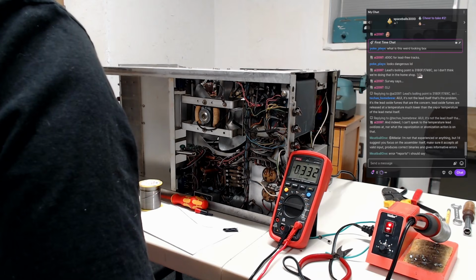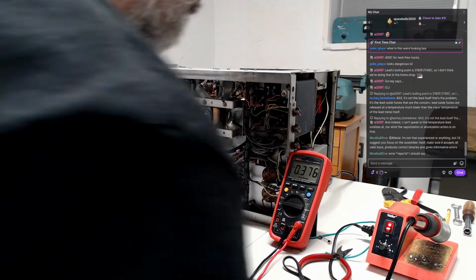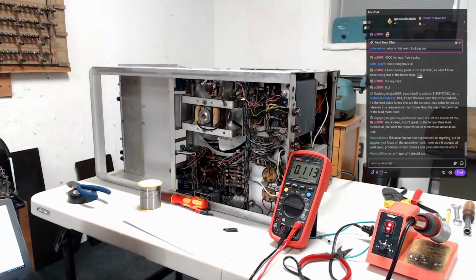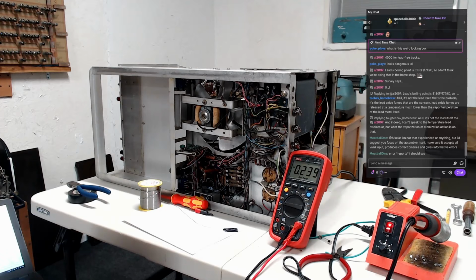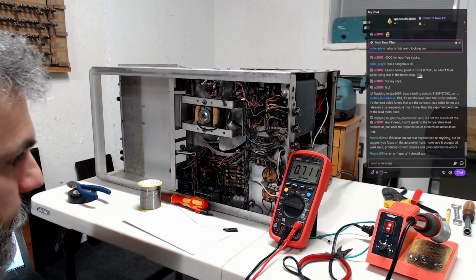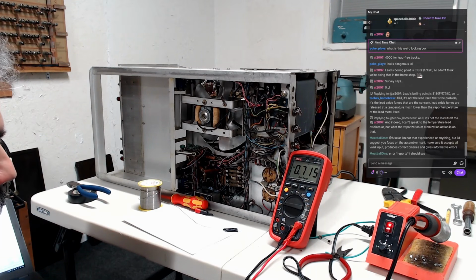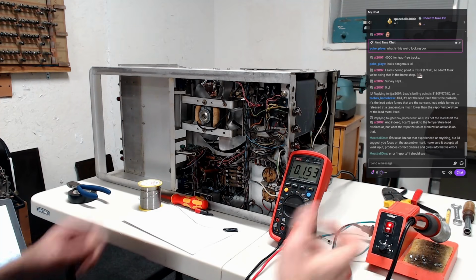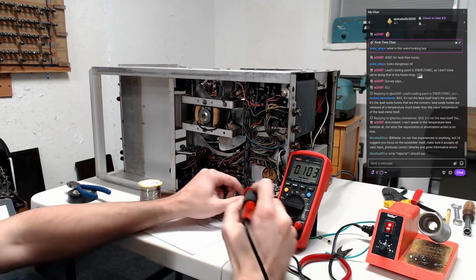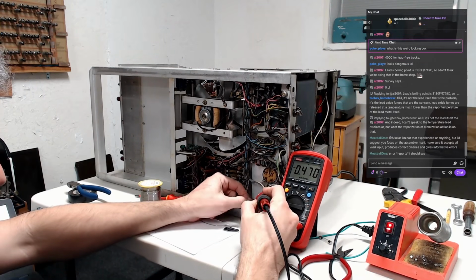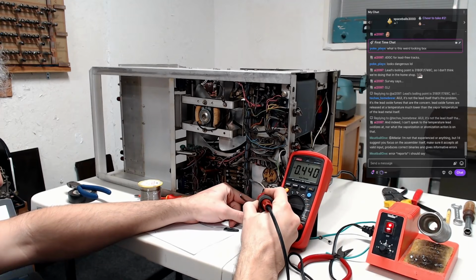Did you test with voltage with T3 completely disconnected? I know you measured it with a meter, but did you test it with live AC voltage? No, we can try that. Disconnect it, connect your meter to it, put a new fuse in, and crank the variac.